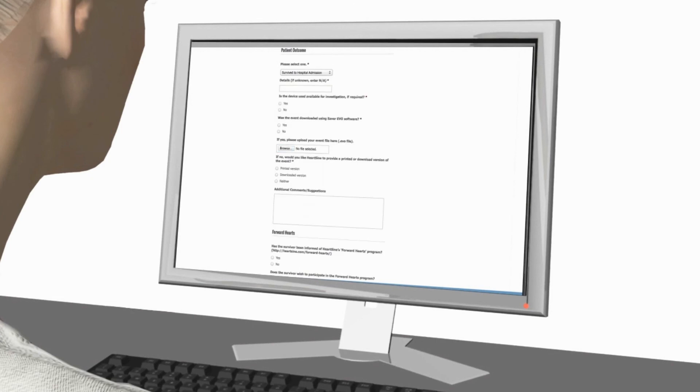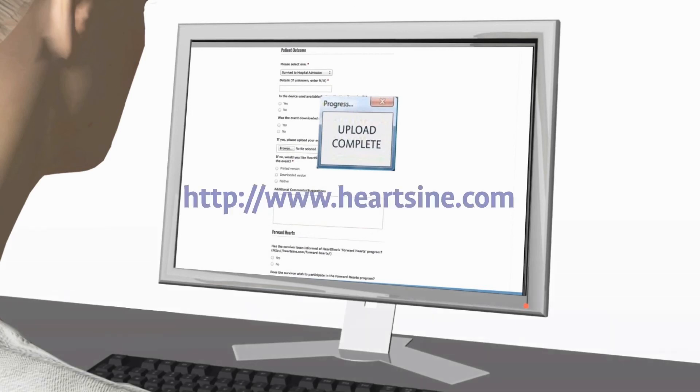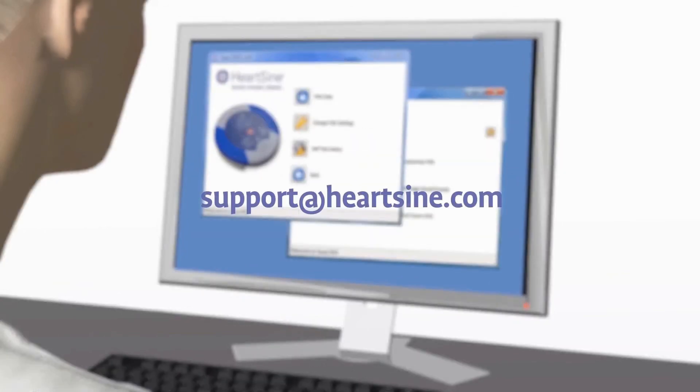After using the Samaritan PAD during a sudden cardiac arrest, submit the Saver EVO file and a completed customer event form to HeartSine, and HeartSine will send you a free replacement pad pack. After downloading the event data, please erase the data from memory. If you need assistance to do this, contact HeartSine Technical Service.